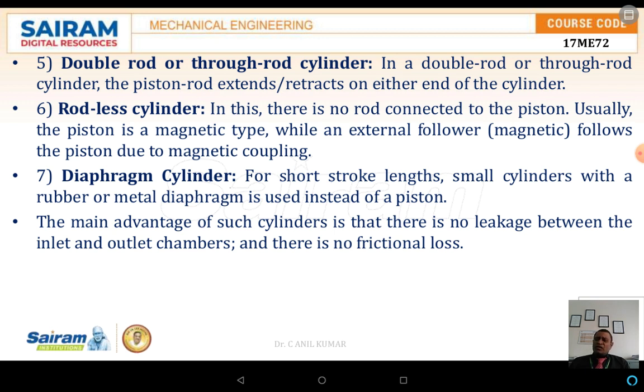The rodless cylinder has no rod connected to the piston. Usually the piston is a magnetic type, while the external follower follows the piston due to magnetic coupling. The diaphragm cylinder has a short stroke length; a small cylinder with a rubber or metallic diaphragm is used instead of a piston. The main advantage of such cylinders is that there is no leakage between the inlet and outlet chambers, and there are no friction losses.